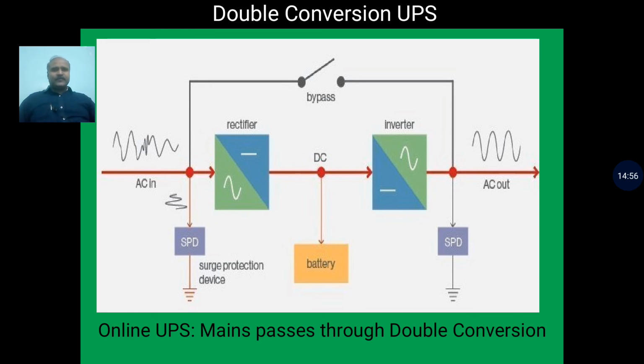Inverter action is independent of AC input. But whenever AC input is present, through the rectifier, continuous battery charging action also takes place. In this case, the online UPS input line is converted into DC power supply after rectification, which is given to both blocks, the battery as well as the inverter. The inverter further converts this DC into AC delivered to the load, and the blocks of SPD, surge protection devices, are shown at the input side as well as the output side. Only when the battery is fully discharged and inversion action can't take place can the inverter be bypassed accordingly.